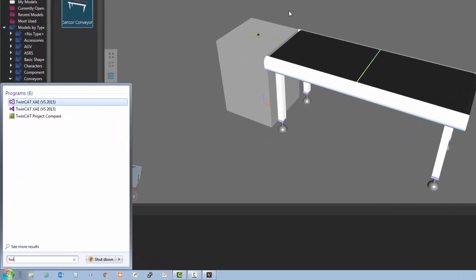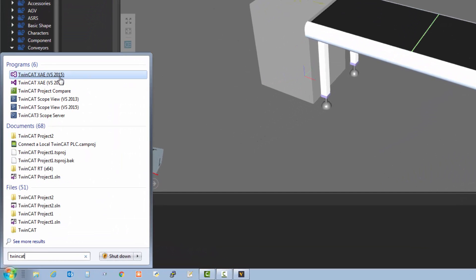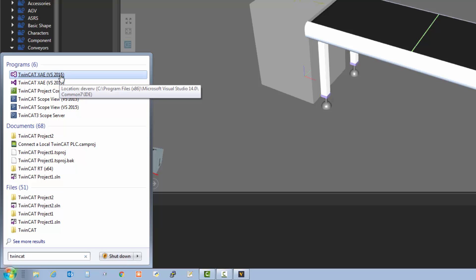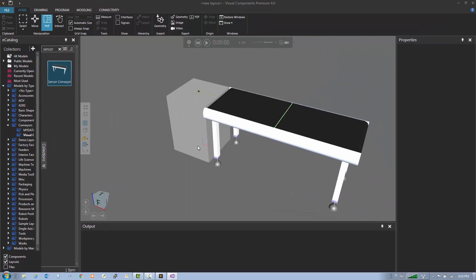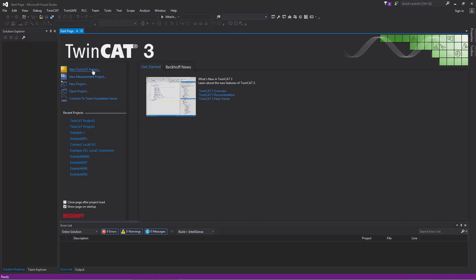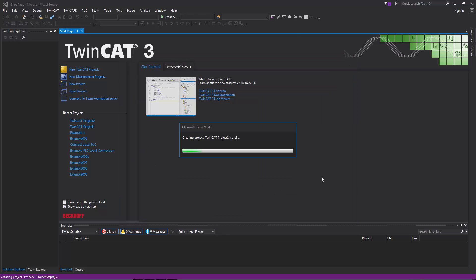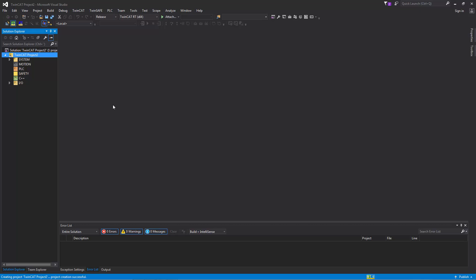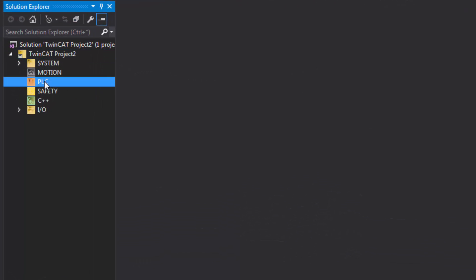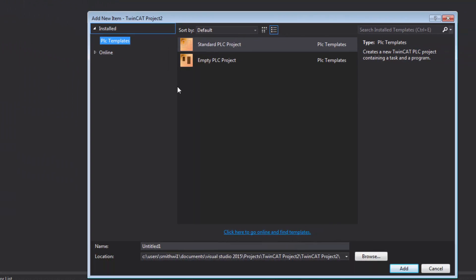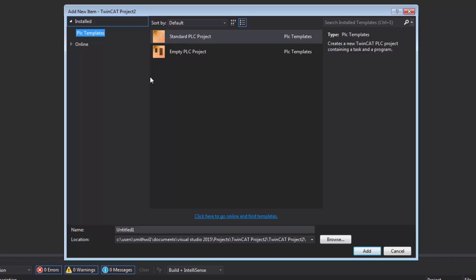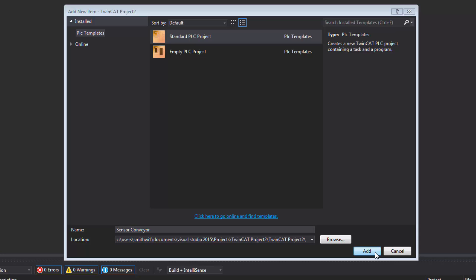Now let's configure our PLC project in Visual Studio. In your Windows toolbar, do a search for TwinCAT — in this case I'm using TwinCAT XAE, or extended automation engineering, with Visual Studio 2015. Run that program and on the start page, click the link to create a new TwinCAT project. You can name the project whatever you want, then click OK and Visual Studio will create the project. You can see it listed in the Solution Explorer pane. Right-click PLC and click Add New Item. We're going to create a standard PLC project that can get the input of a sensor and also send out or write the values of variables in our simulation. Let's rename this project to be 'sensor conveyor' and click the Add button.